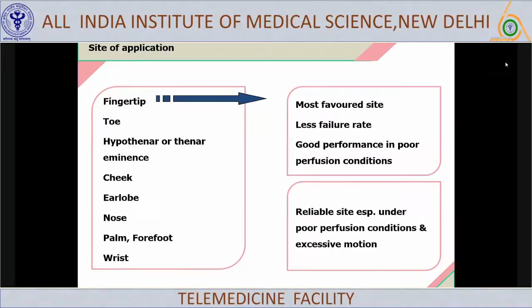Right. So when you apply this pulse oximeter to these patients, these are the key points that you need to remember. The sensor application should be appropriate. That is, whatever probe you are using should be okay. You see there will be a red light and there will be a small window on the other side. The position of this LED and photodetector should be appropriately placed so that the finger comes in between. There is good skin contact. There is proper application site and preparation: it should not be wet, it should not have nail polish, it should not be colored. There should be a reduced activity level, meaning the finger is not moving. If there is an artifact, a movement of the finger, it will show an erroneous reading.